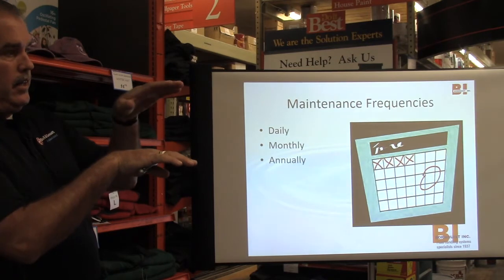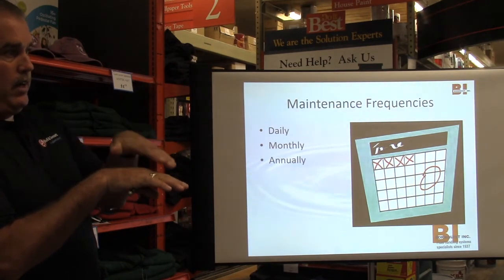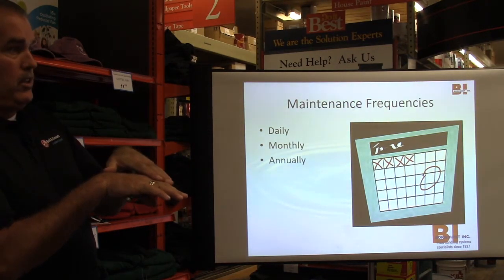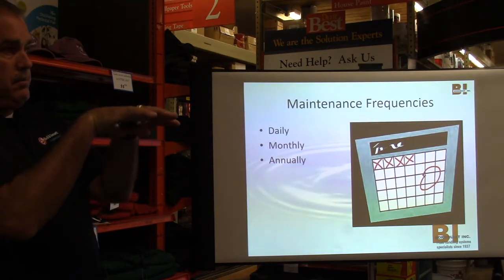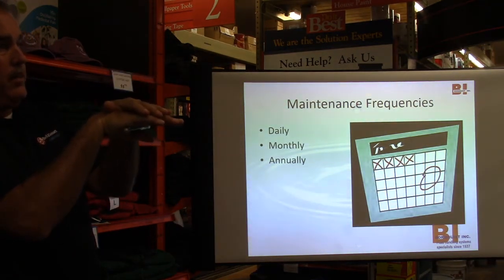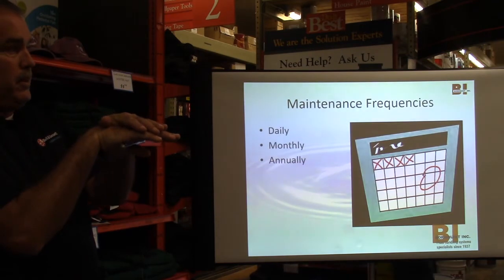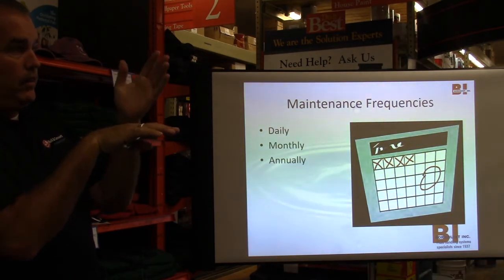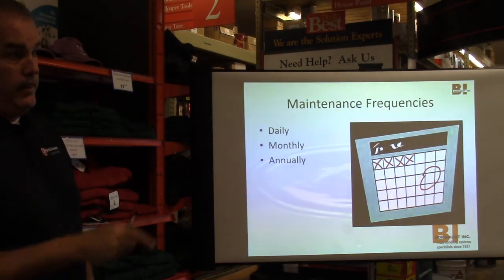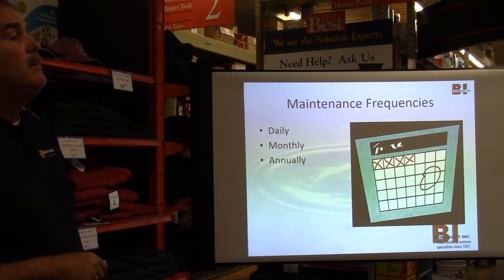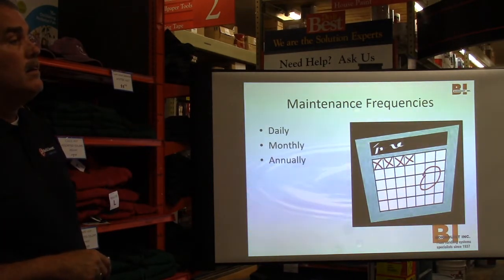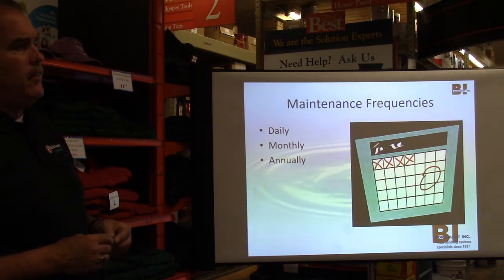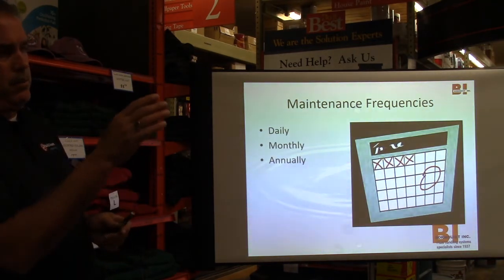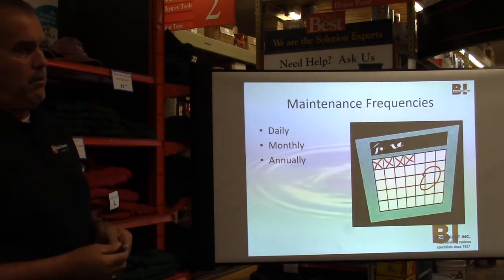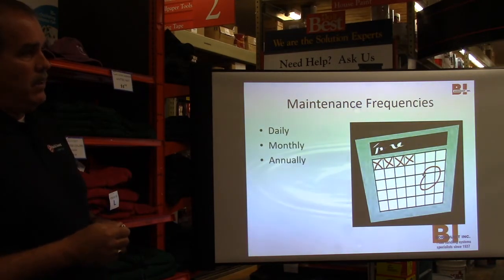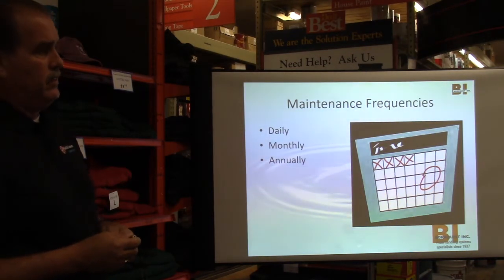So if you think about it, the float drops down following the water line, and at a certain point it shuts off the burner. Well, if that debris keeps building up, the float can drop down and hit the debris before it turns off your burner. That'd be great, right? And now your low water cutoff isn't doing anything. And that's why they do blowdown. Gotcha. Thanks. You do it a lot more often than once a week? No, not on a residential application. I would actually say once a week is if you've got kind of crappy water. But really, once a week is more than sufficient.